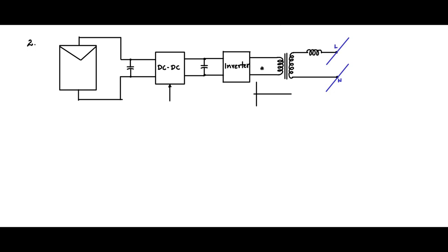If you look at the inverter output, it will be a switched AC waveform. If I draw the waveform versus time, you will see a pulse-width modulated switched waveform. The PWM waveform is switching at high frequency but the fundamental is 50 Hz, which when filtered by the inductor will give a filtered current — almost smooth at 50 Hz but with some switching harmonics.